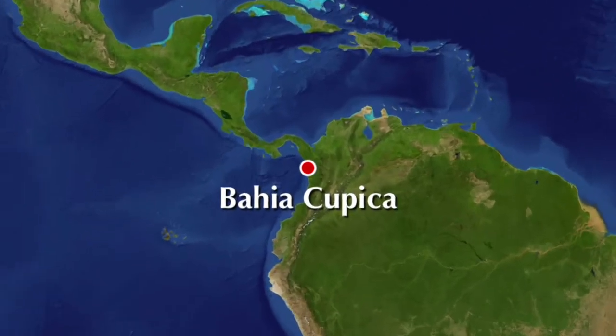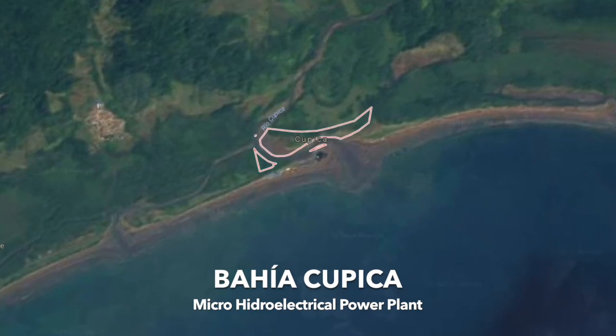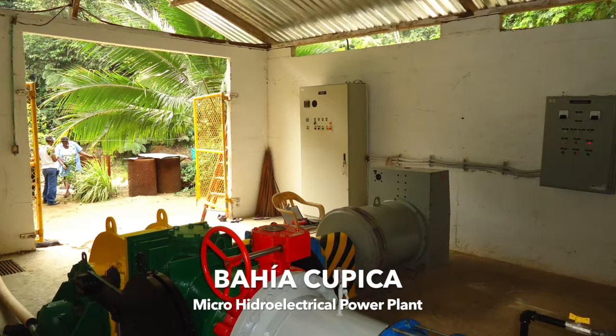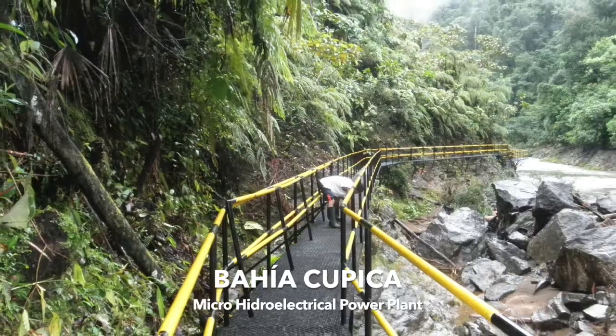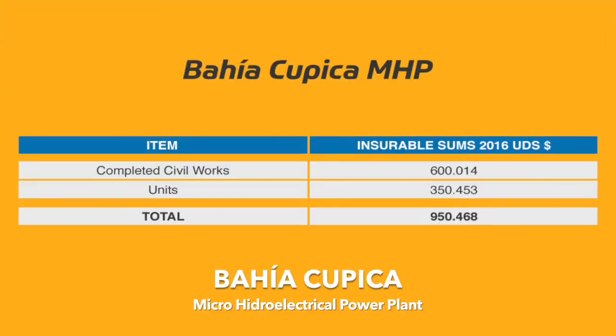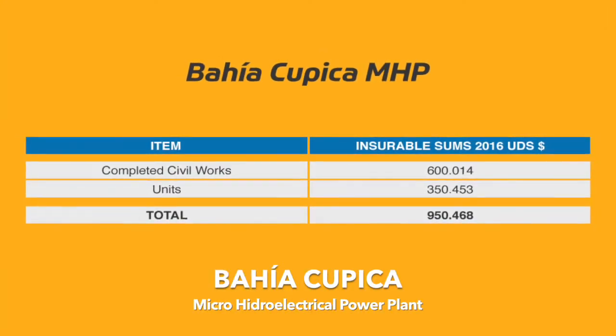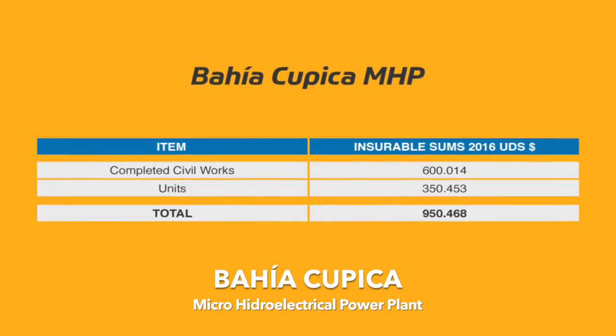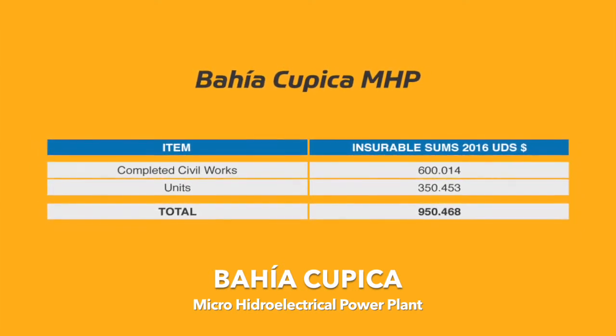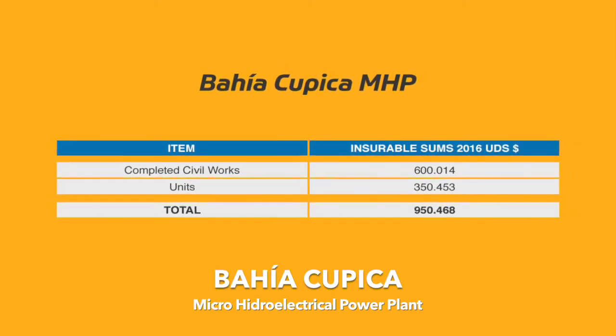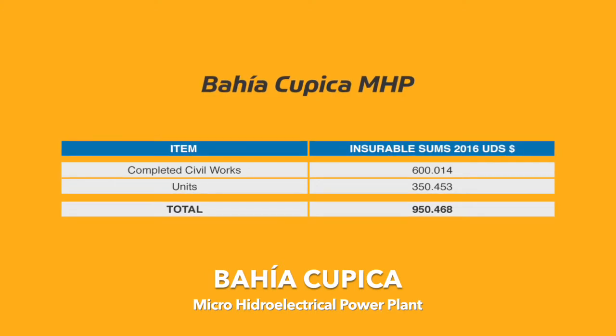Bahia Cupica Micro Hydroelectric Plant. The generation system of the Bahia Cupica Micro Hydroelectric Plant consists of 1 hydraulic unit of 400 kilowatts, 1.5 MVA substation with a 0.5 MVA backup transformer, and 1 transmission line of 13.8 kV between the plant and the distribution center.